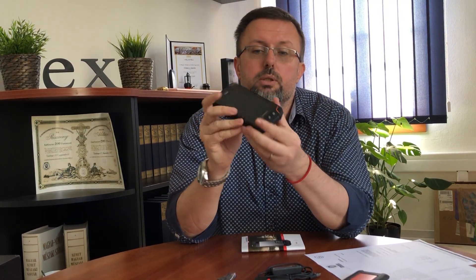At the end of the certification marking you will find an 'X' sign. This is about special conditions of safe use. You can only use the battery pack from the manufacturer, only the charger from the manufacturer. It needs to be charged outside the EX area — the access point is found below the cover. It needs to be protected against high impact, UV light, and electrostatic charge.